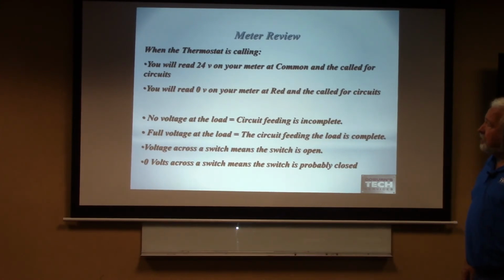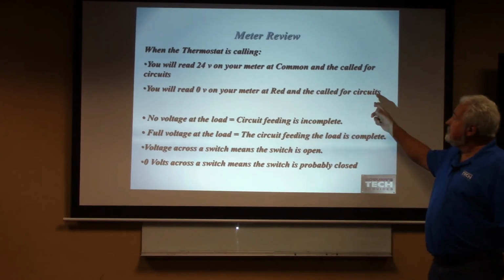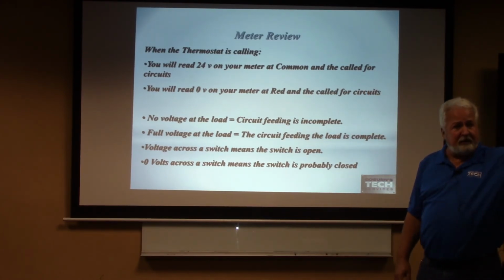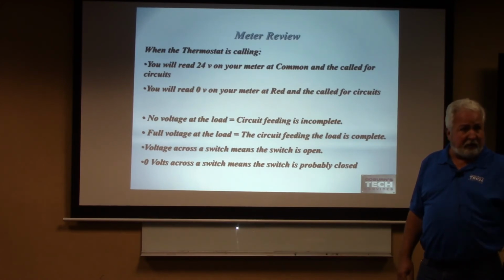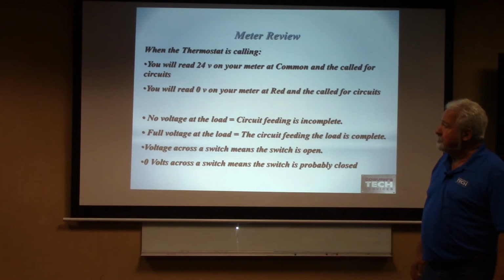When your thermostat is calling, you will receive 24 volts on your meter at common and the called for circuits. Does that make sense? When your thermostat is calling, you'll receive 24 volts on your meter at common and any one of those circuits it's calling for, whether it's calling for heat, cooling, fan. Good? You'll read 0 on your meter from red to the called for circuits, because the red is our switch, red to whatever. So you're going to read 0 across a closed switch.